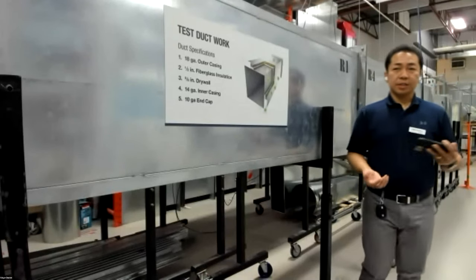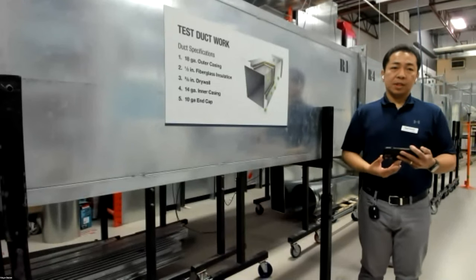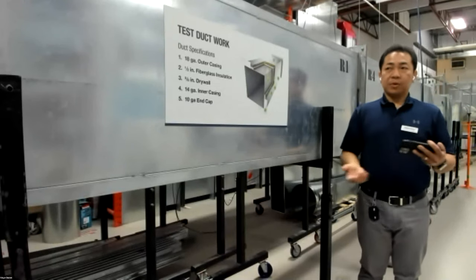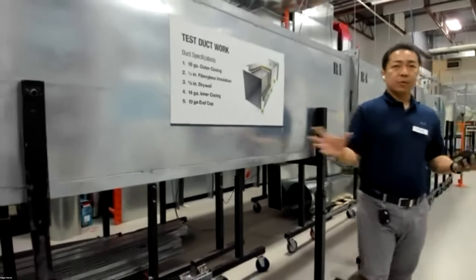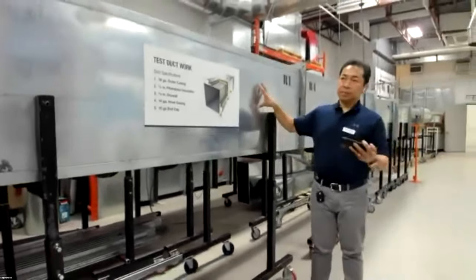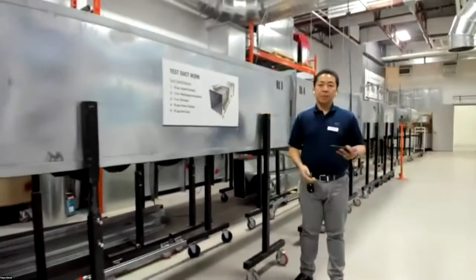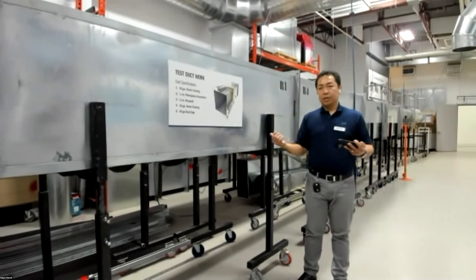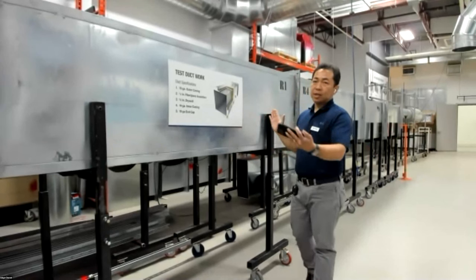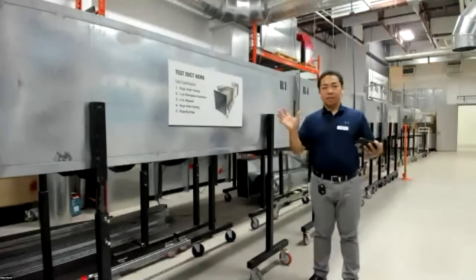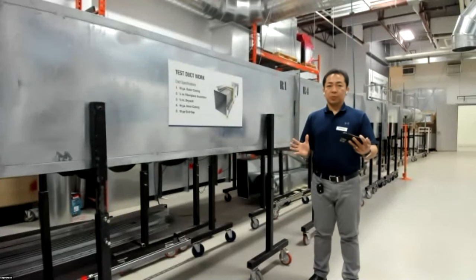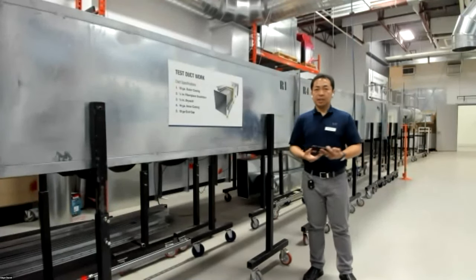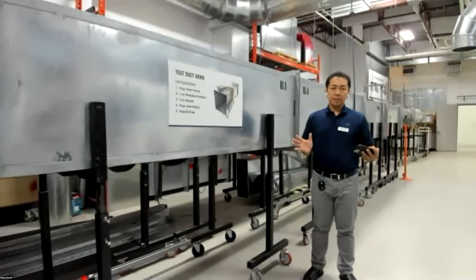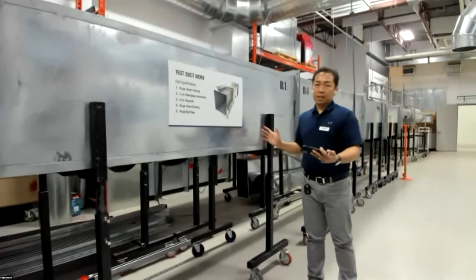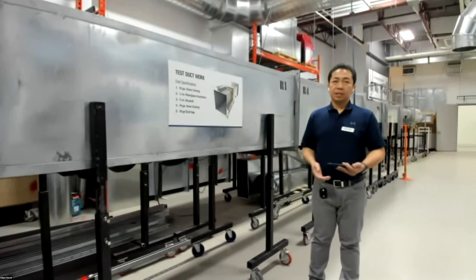The way we test silencers, maybe I'm just gonna give you a brief overview, and Chris might give you more in detail. So with the silencers, we put the, we call it empty ductwork. This is the empty ductwork. There's no silencer yet. This is our baseline for testing silencers. We run with and without airflow. And then we put the silencer in with the same duct section taken out. And then we test again the same test points. The difference would be the insertion loss of the silencer, as well as we also test generated sound noise in conjunction with the insertion loss.